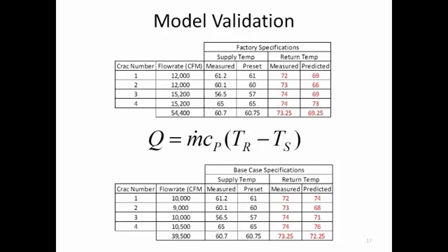But again, this is all within the realm of getting your hands around the big parameters and trying to understand how to steer the ship in a big ocean. So, getting your hands around some base parameters and understanding, and I felt fairly good about this because I got my temperatures to line up fairly good. That's all I had to go on at this point. I've had other studies where they've gone around with a balometer and measured flow rate coming out of the tiles. That's a good thing to calibrate. Anything you can do to validate.